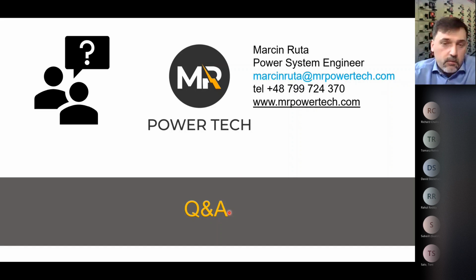Now, if you are measuring something, or just making a switching operation on off, I can say, okay, everything designed according to IEC is supposed to be safe, and that's fine. Then we add the next layer: we calculate what the arc flash level is, and now you might say, okay, my switchgear is designed according to IEC, but also arc rated according to 61641 technical report. So we know up to 15 kiloamps, 300 milliseconds, the arc will stay inside. And then you say, okay, whatever we operate, in normal operation, things happen inside and they stay inside. So we don't need any additional arc flash PPE for doing our work.